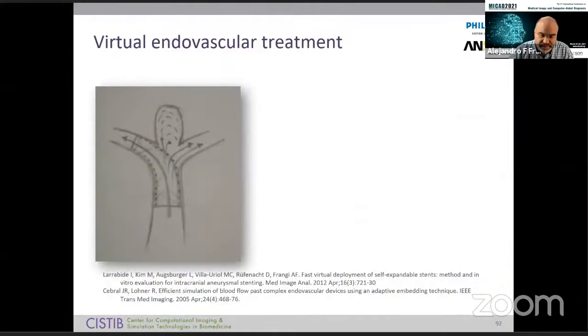I like to show is that, when I was doing this work some years ago, I asked one of my interventional radiologists from Switzerland, Daniel, how do you actually think about these devices? And he said, well, we normally put a stent in a particular direction that will reduce the blood flow going to the aneurysm, producing a stasis and therefore blood clotting. But there will still be a low resistance distally to the vessel, and that will mean there is still a flow going through the struts of the stent down, so I don't close this vessel.